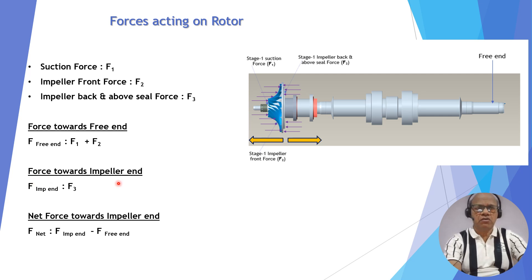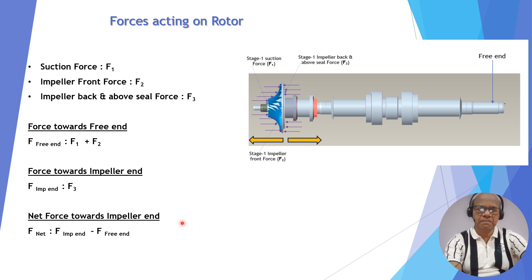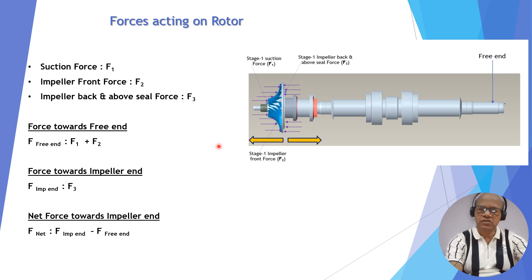To summarize the force balance: forces toward the free end equal F1 plus F2; forces toward the impeller end equal F3. The net force toward the impeller end is F3 minus (F1 + F2). If this net force is positive, the rotor thrusts toward the impeller end; if negative, the rotor thrusts toward the free end. So when F3 is greater than the sum of F1 and F2, the rotor goes to the impeller side; when F3 is smaller, the rotor goes to the free end side.